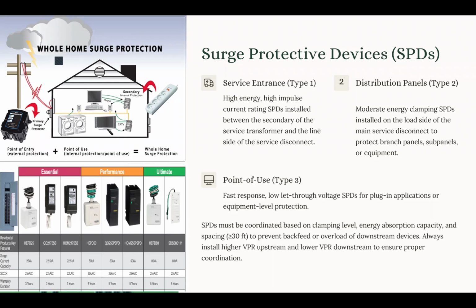Now we have several classifications for the surge protective devices. One would be the type 1, the service entrance, which is installed between the utility service and the line side of the main service disconnect. The function is to divert the high energy surge from the external source, so it would not propagate downstream into our system.